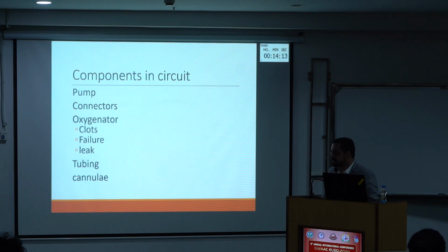If you have clots, it goes to oxygenator failure, and there are sometimes leaks in the oxygenator. Sometimes plasma leak does happen. In those situations, you need to change. And then tubings. If there is a sudden disconnection of the tubings, or there is a clot in something like the cannula, that also warrants a change, starting from cannulas. So these are the various parts.